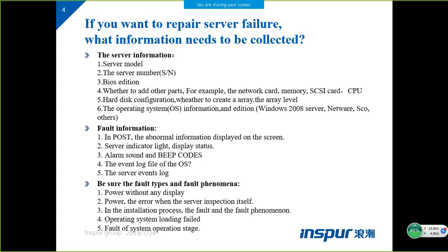Any abnormal information displayed on the screen, and whether the server indicator light is red or green, blinking or stable, and the alarm sound, and any logs from OS or BMC, and be sure of the fault types and fault phenomenon.